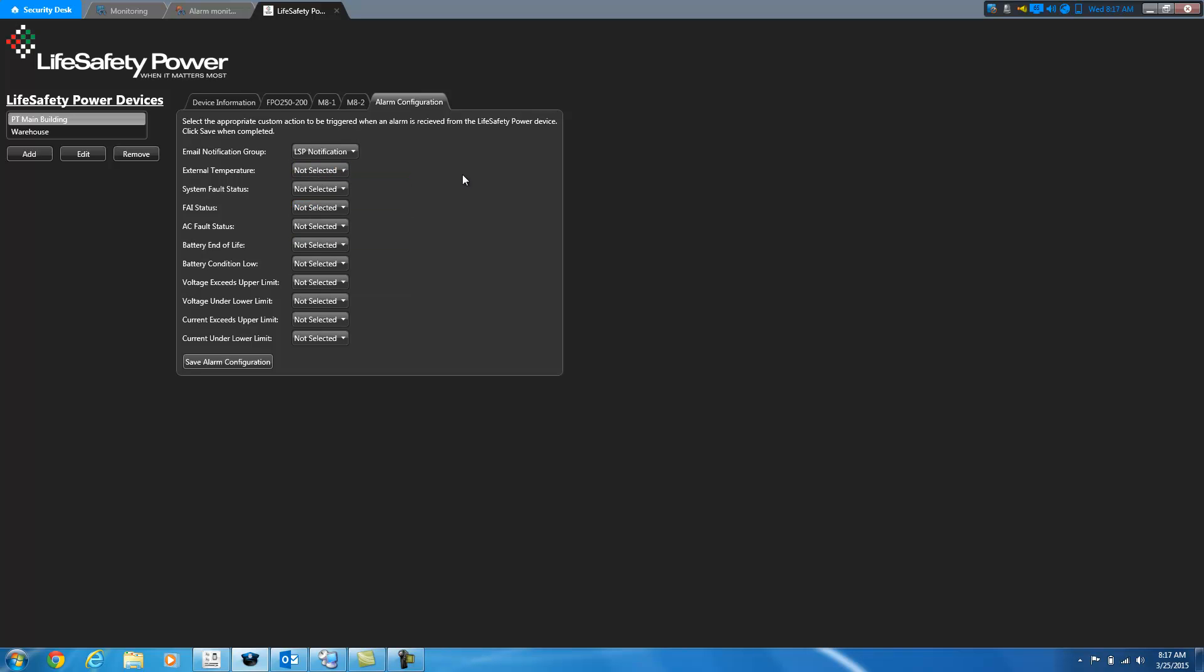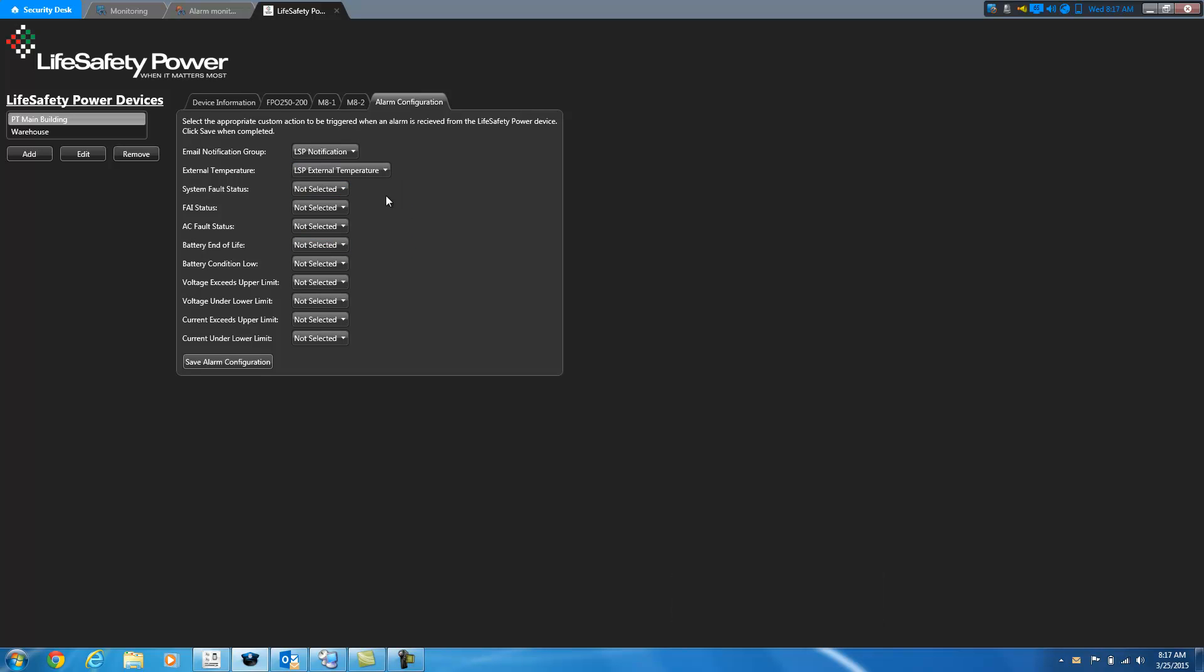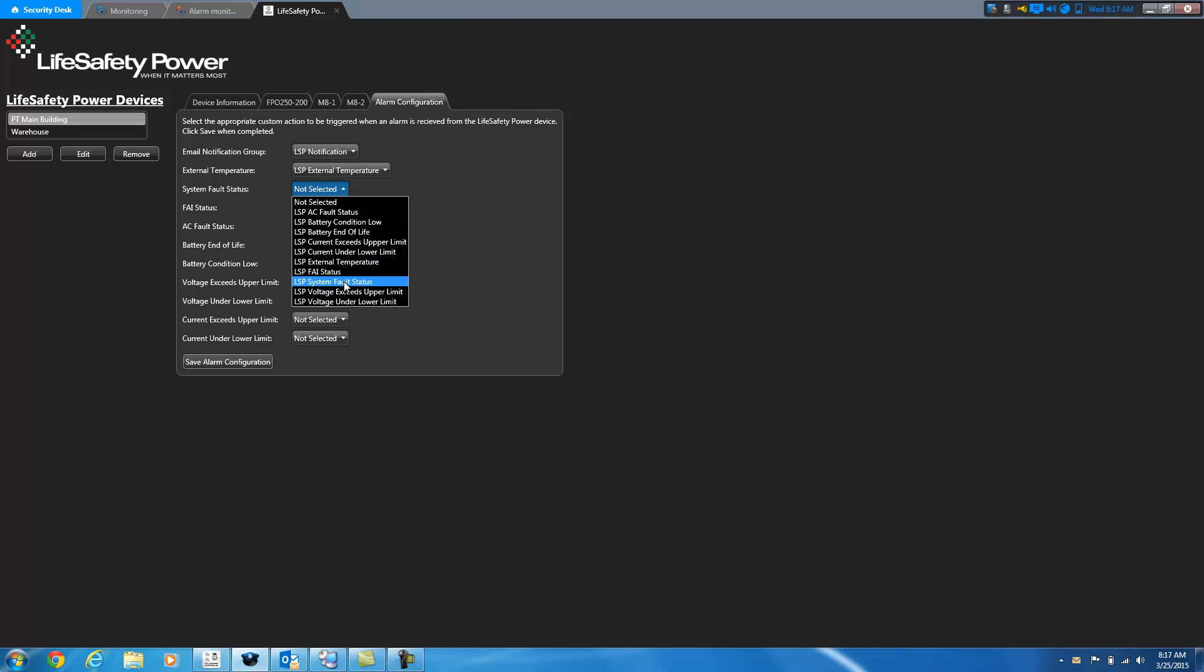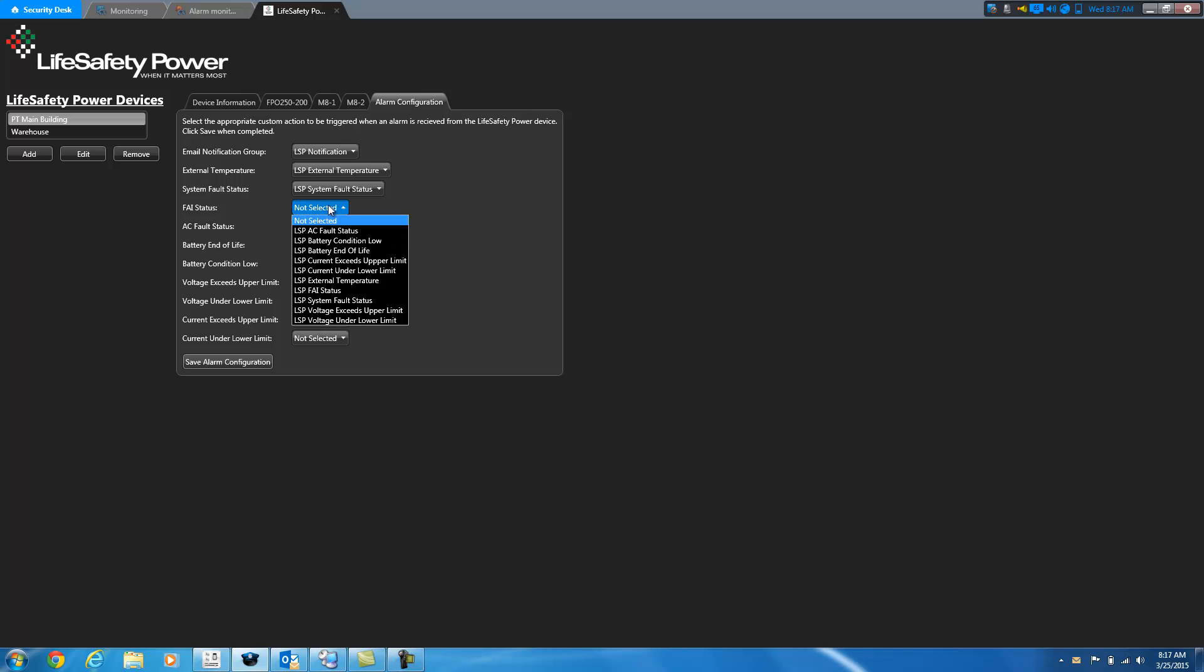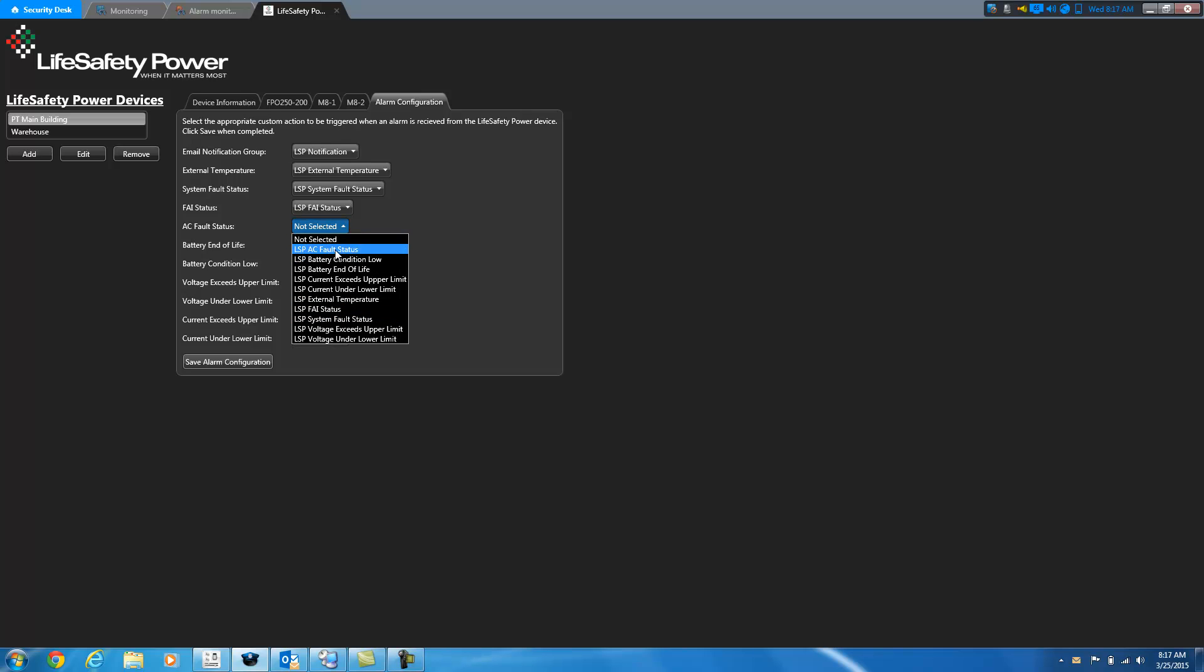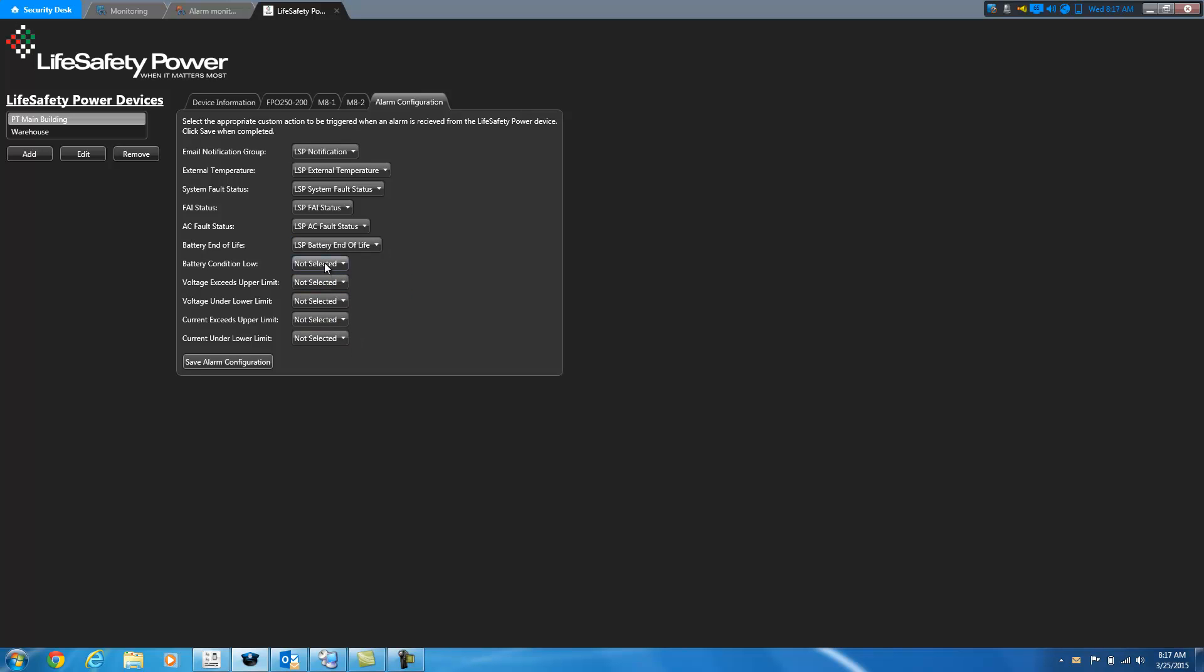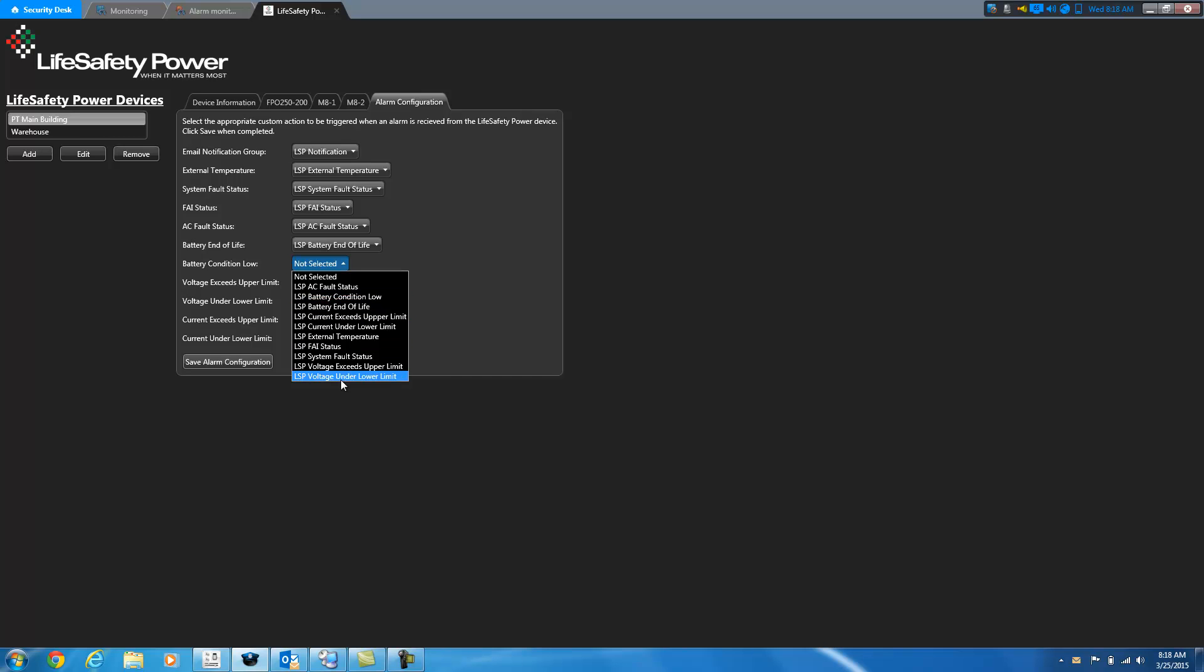The rest of these, external temperature system, fault status, etc., these are events that are sent out by the device. And then you can select custom events that you've configured inside the Genetec system to be raised when those events are received. And then you can create event actions to do additional things with inside the Security Center software based on when those events are raised. And I have a couple of alarms set up to be triggered when the voltage exceeds or goes under the configured limits and also for the current.